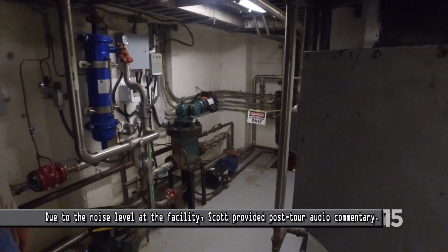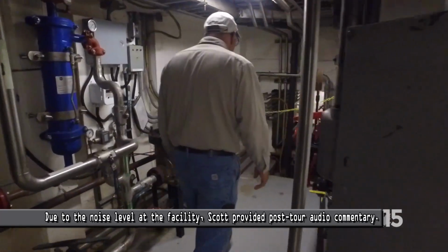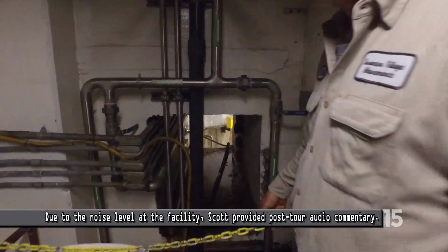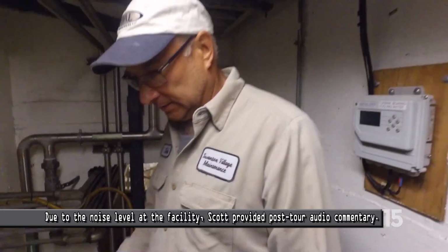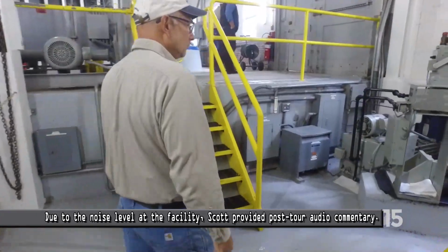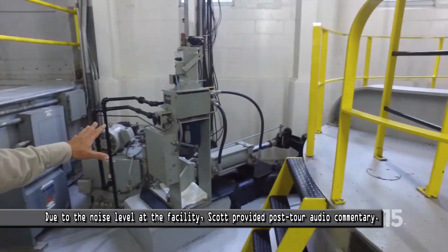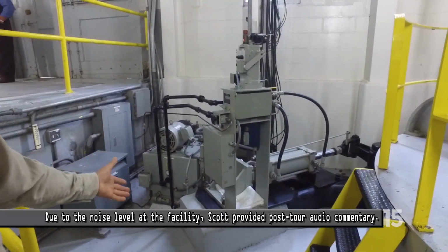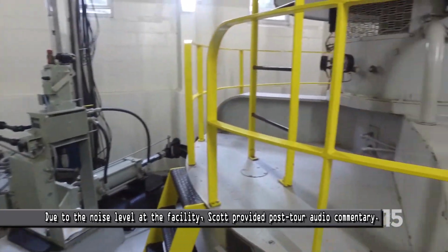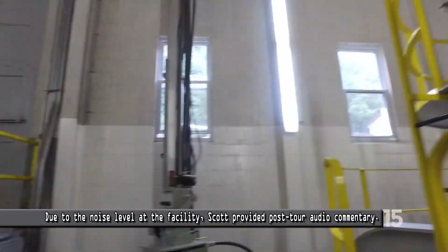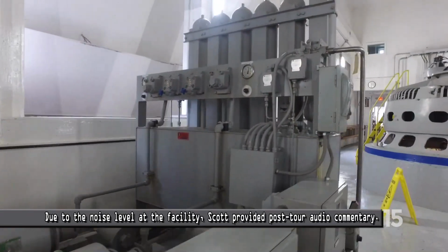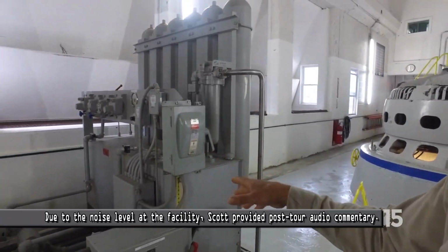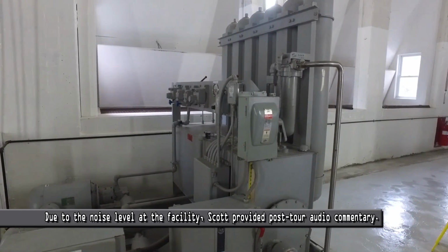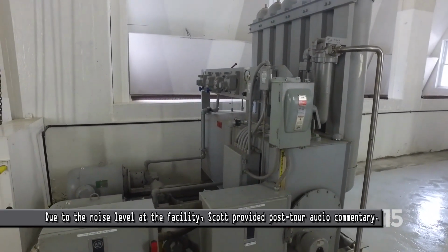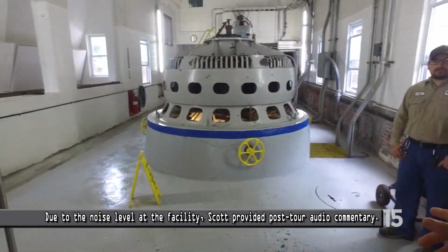We also have a similar cooling water system as Unit 4, where we bring in penstock water, pressurize it, and run it through a centrifugal strainer as well as a rotating automatic strainer. Here we have the governor and the HPU for Unit 3. Each unit has a governor and an HPU. The HPU provides hydraulic pressure to the piston that opens and closes the wicket gates, providing water to the runner, spinning the unit. This is the butterfly valve hydraulic pressure unit, providing hydraulic pressure to the 4 pistons that operate each individual butterfly valve, providing water to each unit.